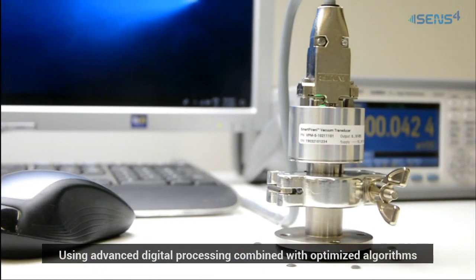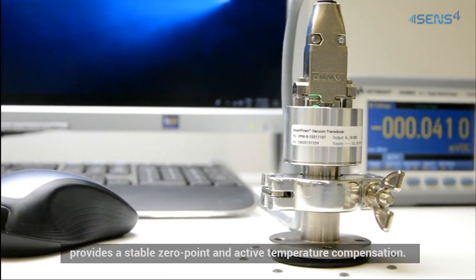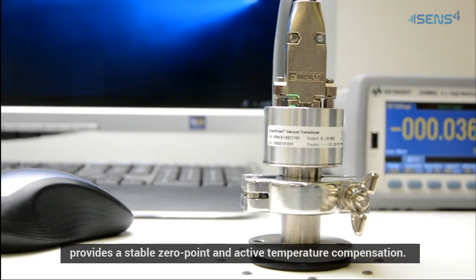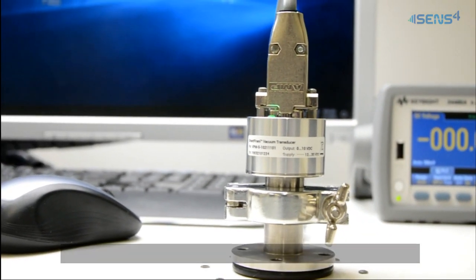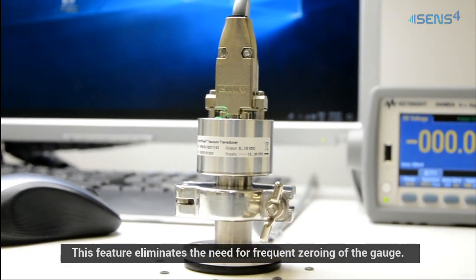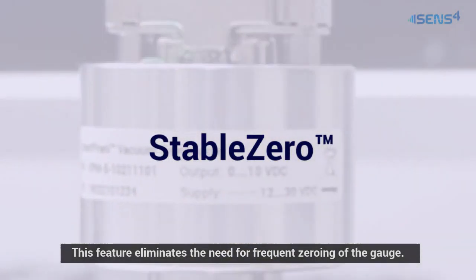By using advanced digital processing combined with optimized algorithms, it provides a stable zero point and an active temperature compensation. This eliminates the need for frequent zeroing of the gauge.